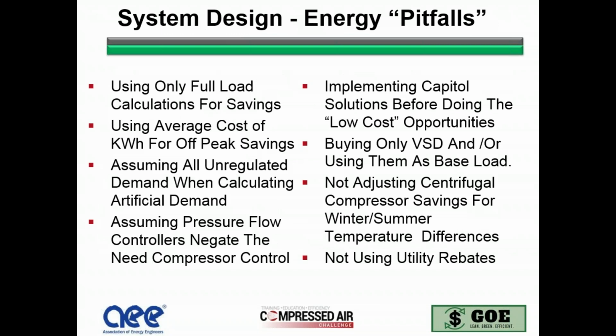So some of the design pitfalls, again, this is a real high overview. You'll be able to learn more if you go to the Compressed Air Challenge Fundamentals and Advanced classes, but this will give you a flavor of just some ideas and things to think about that we go into much more detail in the trainings. So when you're starting to do design projects, using only full load calculations for compressors, most of the time the compressors will stay in a partial loaded state and not at the full peak load.